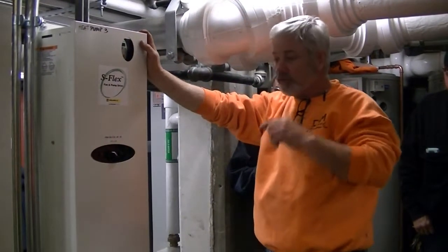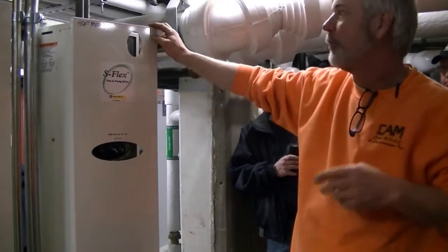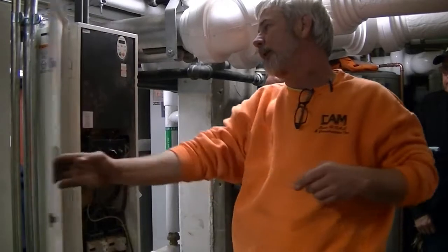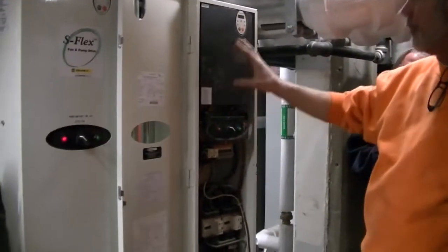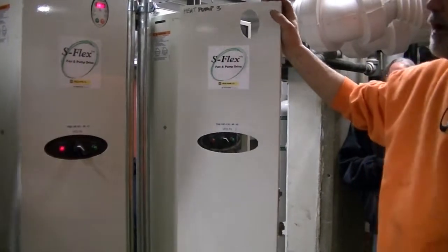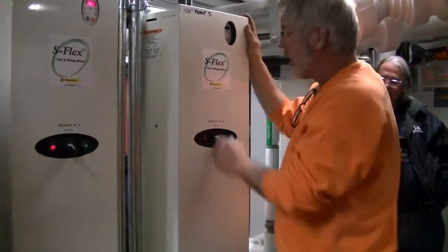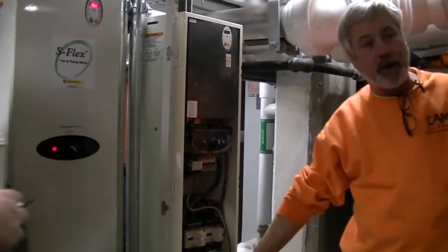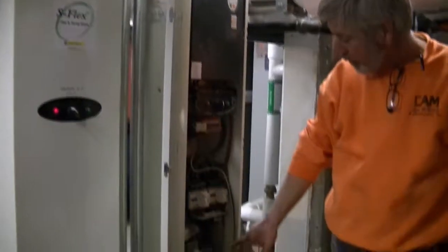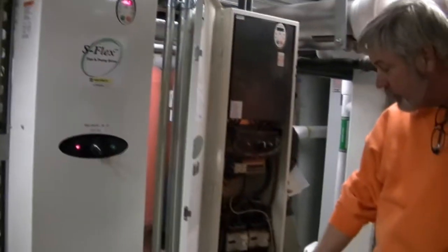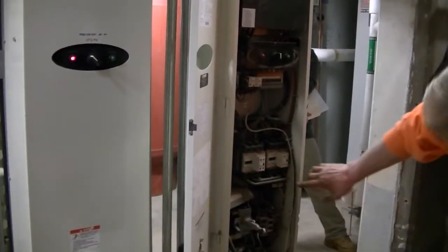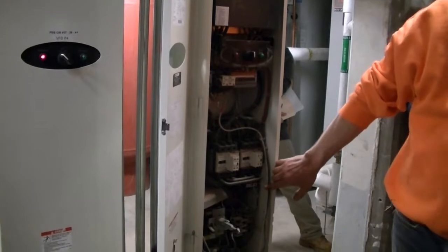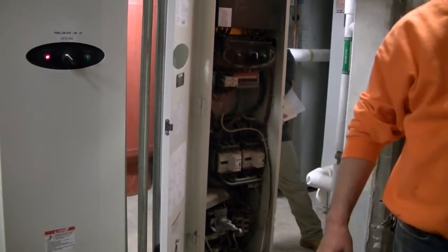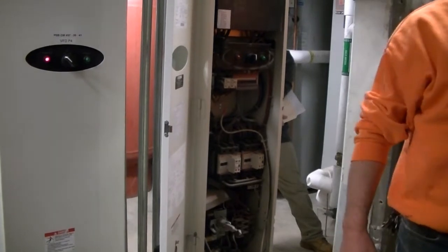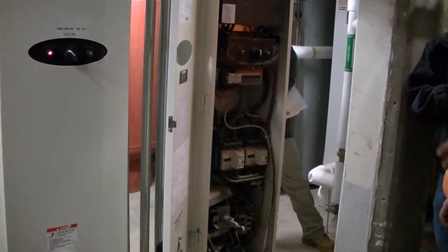I'm going to start by taking you through the main building heat drives. These are pumps 3 and 4. What we have is a VFD, which is a variable frequency drive. When you open it up, kill the power, turn the drive off, 3 latches, the door will open. You notice there's a circuit breaker here. This is a resettable circuit breaker. There are fuses on the step-down transformers. And there is a manual reset overload if you ever have to put the drive in bypass, which you should seldom, if never have to do unless something goes catastrophically wrong in the drive.